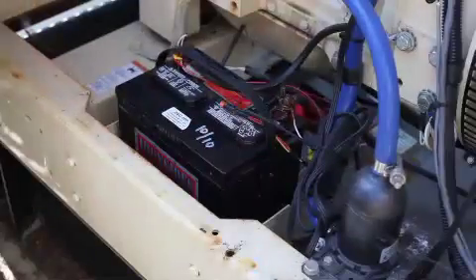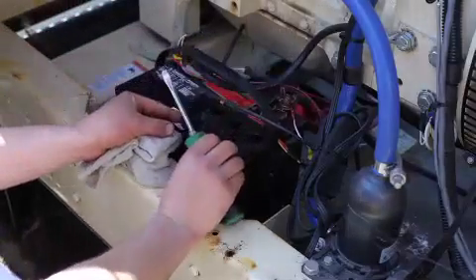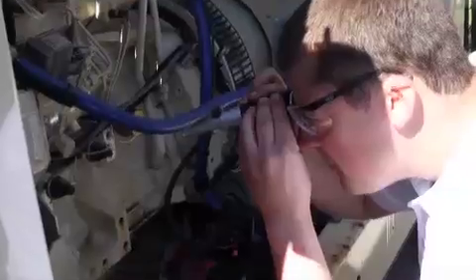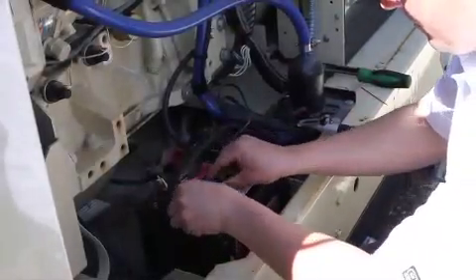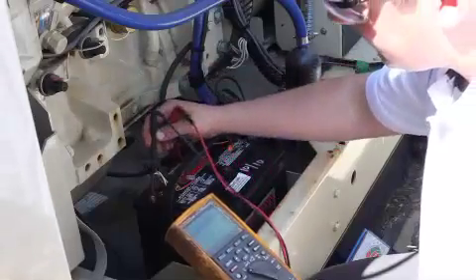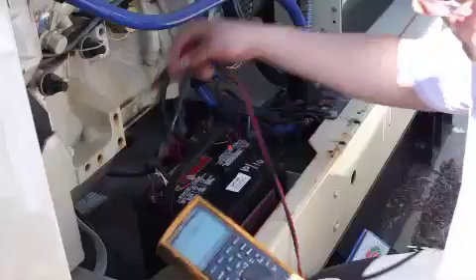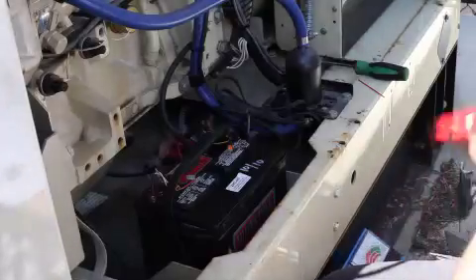A typical planned maintenance contract visit will carry out battery maintenance service and checks, including checking all battery and starter connections, removing cell caps and checking electrolyte levels, and taking electrolyte samples to examine with a visual test device. Replace caps after checking, and examine battery cleanliness. Connect an electronic tester to verify battery cell voltage when stationary and during run-up. If the tester reads close to battery voltage at no load but drops significantly when the load is applied, it is a strong indication the battery needs replacing.